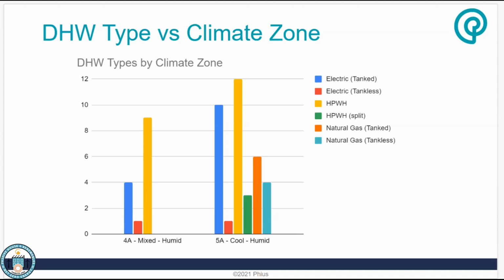The heat pump water heater split, the green one, basically represents where the condenser and the water storage tank are separate from each other. The condensing unit is on the outdoor side, that's basically the Sanden CO2 heat pump water heaters we're referring to for the most part, when it's a split heat pump water heater system. In the Sanden unit, for example, CO2 is used as refrigerant to connect the outdoor condenser to the indoor water heating tank, to accomplish the same thing as a heat pump water heater, but rather than having them in one combined unit inside the building, it's split into two separate pieces.